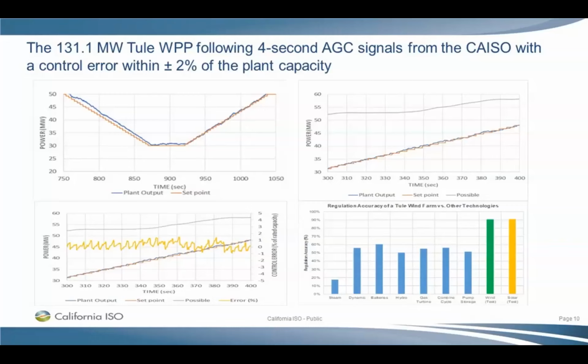When you look at the error in control at the bottom left, it's within 2%, which is really accurate. And then in the lower right, we compared different categories of resources, like combined cycle plants, hydro plants, things like storage. But if you look at the green bar, it shows a wind plant could follow a regulation signal with above 90% accuracy, whereas the other plants, because they have rotating mass, perform at around 60% or less. So it tells you wind plants can perform very, very well.